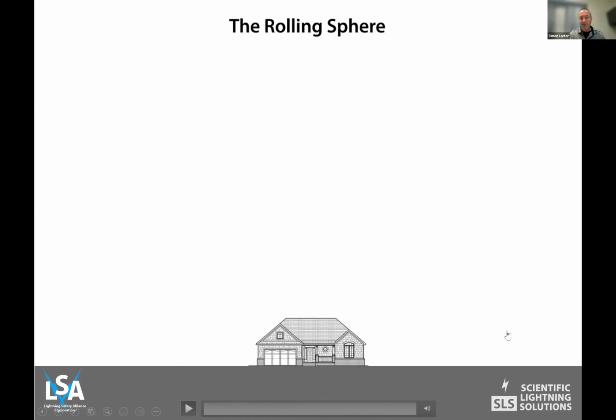How do we figure out where to put the lightning rods? Here's the operating principle we work with: the rolling sphere method. When the stepped leader comes down towards ground, a counter leader rises up to meet it, reaching it roughly 30 to 45 meters above ground. That's the final point where the circuit completes and the current can flow. That jump, that counter leader coming up, is the final breakdown of a lightning strike.